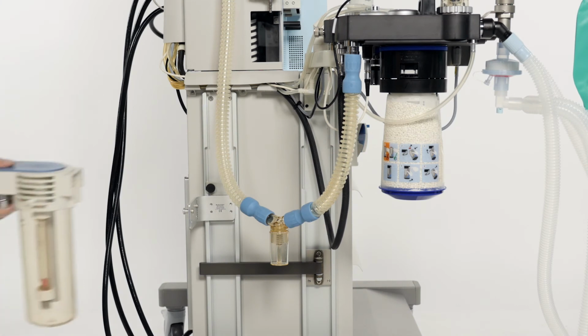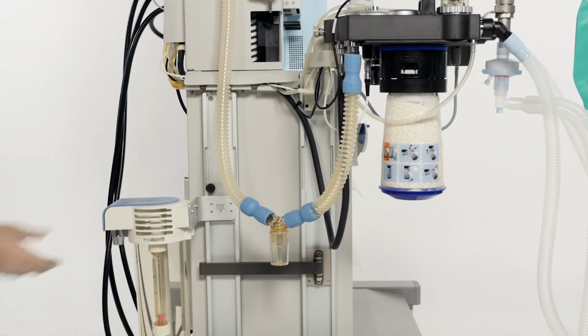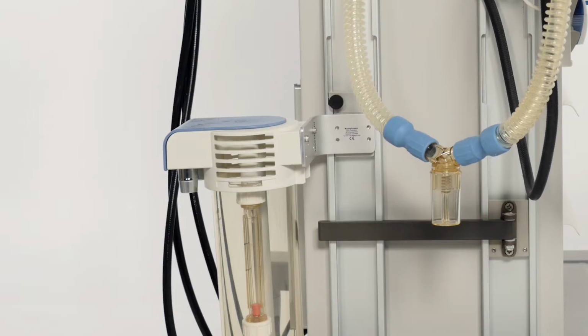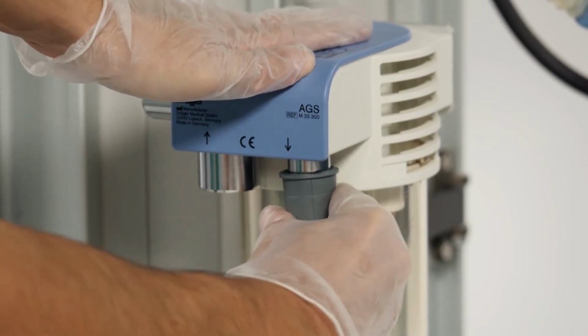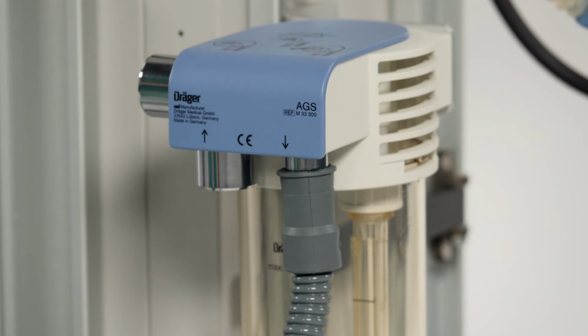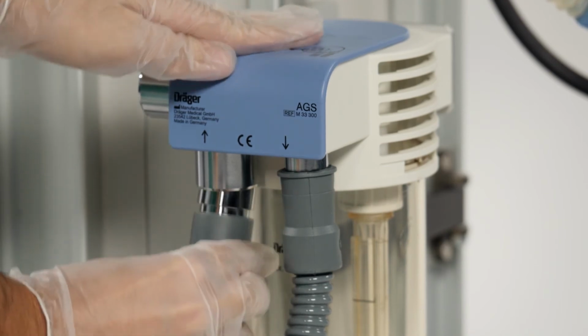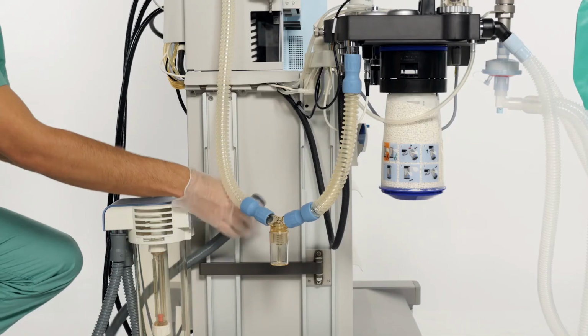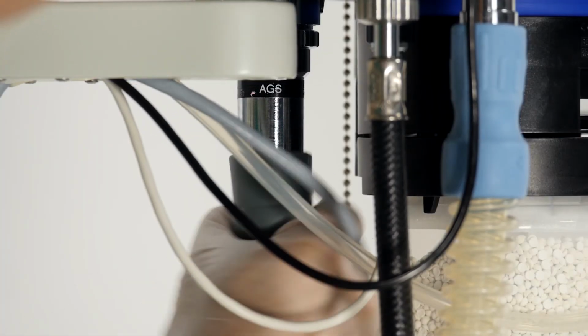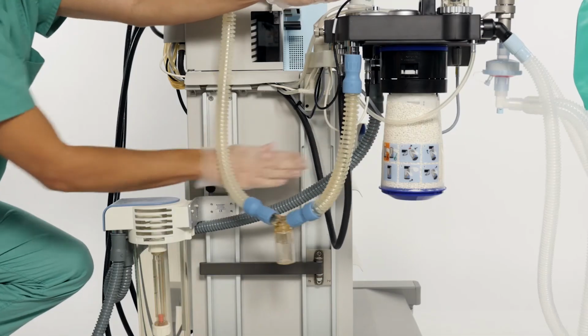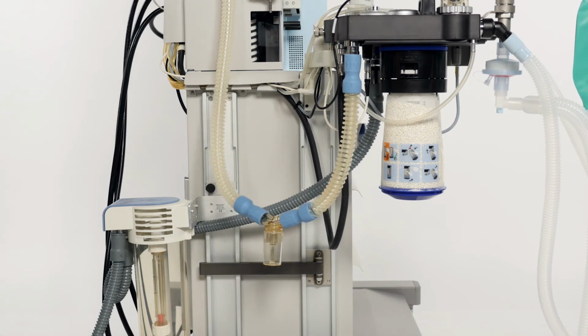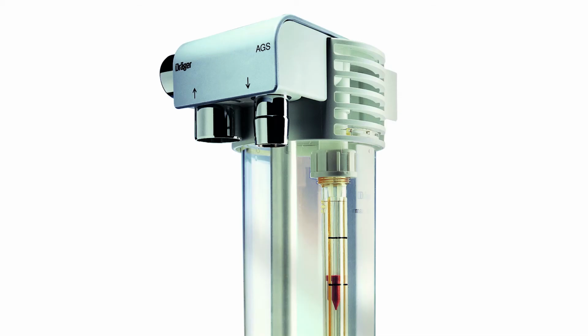For the assembly of the anesthetic gas scavenging system, hook the receiving system into place on the rear side of the Fabius. Connect the scavenging hose from the receiving system to the central disposal system. Then connect the transfer hose between the breathing system and the receiving unit. To check correct operation of the waste gas disposal system, the float indicator in the flow tube should stay between the upper and lower marks.